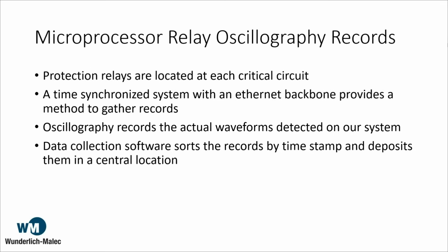We have a system where we're going to gather oscillography records. That's the record of how the relays saw the fault and triggered, on a time-synchronized system with an Ethernet backbone. Nowadays we can do time synchronization over TCP/IP, which is great. We're going to grab those records from the relays, sort them by timestamp, and put them in a central location.